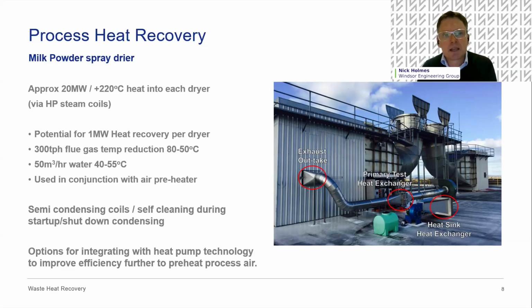The hard thing to get these projects off the ground is the top of a spray dryer, specifically in New Zealand with seismic constraints. A big coil is a lot of weight, and it hasn't been designed to accommodate that. There's a lot of piping to get that hot water down into the preheater coils, the steam coils, the air heaters. So there's a lot of logistics to make it happen. But in theory, it's all doable. Probably for a new build, it would go without saying this would happen.